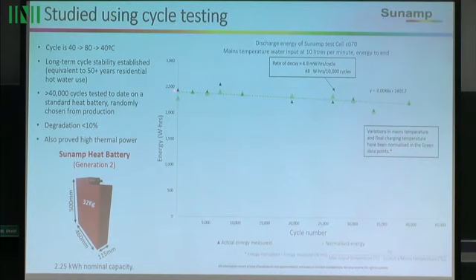So we've got about 48 watt hours of reduction per 10,000 cycles, fitting a straight line, though maybe we should fit a curve instead. If you took the early part of the curve out to about 20,000 cycles, the rate was about 25 watt hours per 10,000 cycles, on a device with 2,250 watt hours of capacity. So you can go 40,000 cycles and get less than 10% degradation. If I could do that with lithium ion, I'd be one of the richest people in the world today.